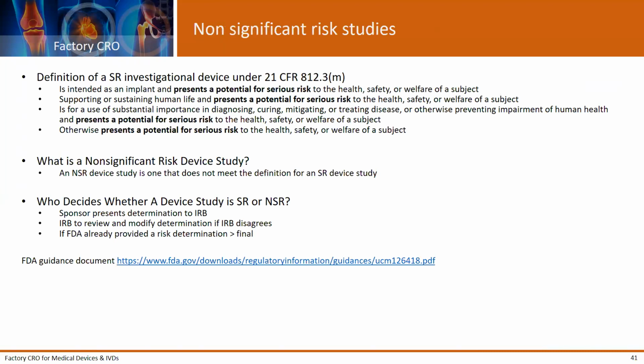So I do understand that manufacturers of medical devices want to stay away from such an effort. So is there anything else that can be done? I would like to point out that there are non-significant risk studies which do not need involvement of the FDA.